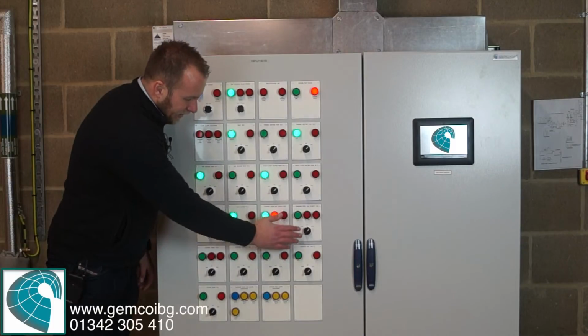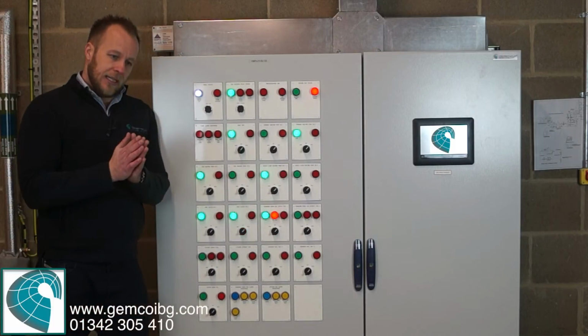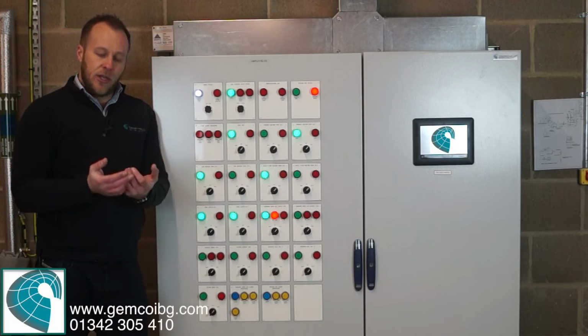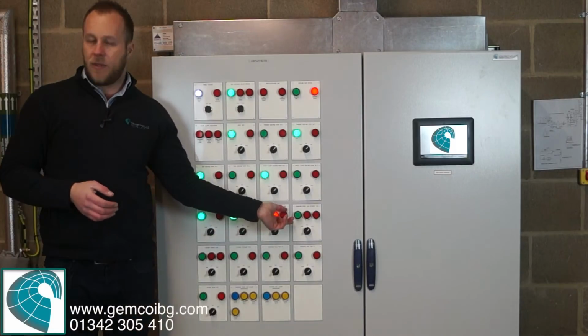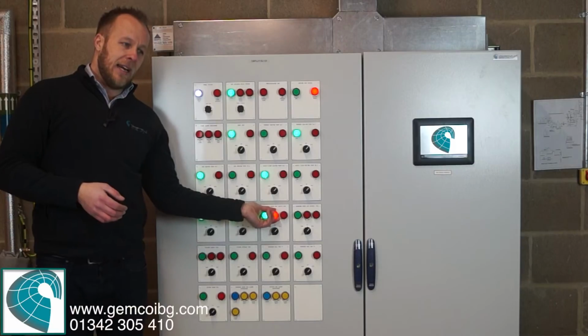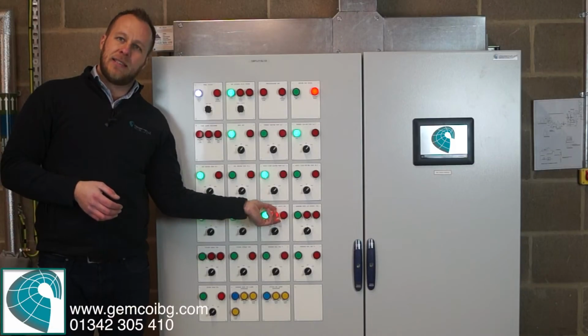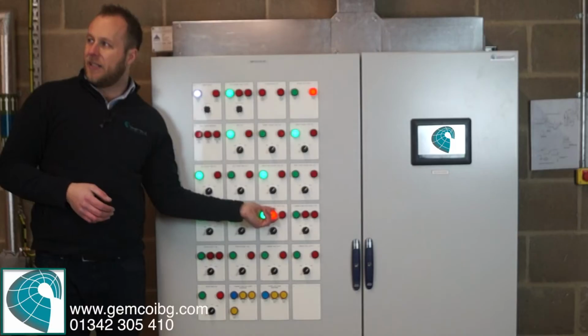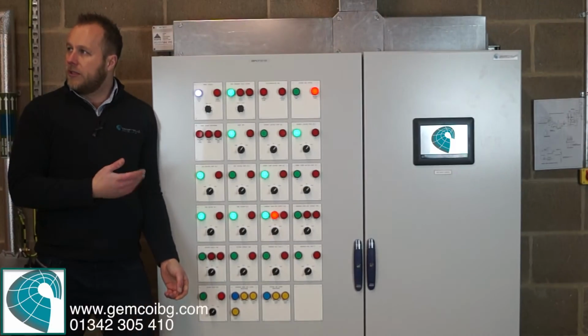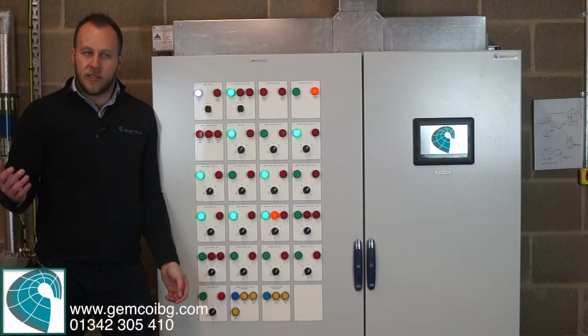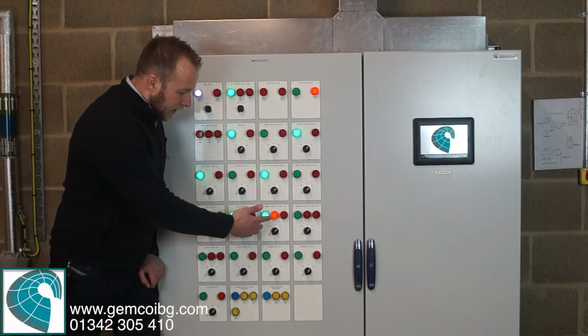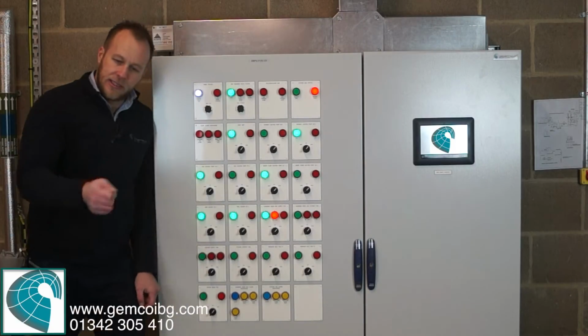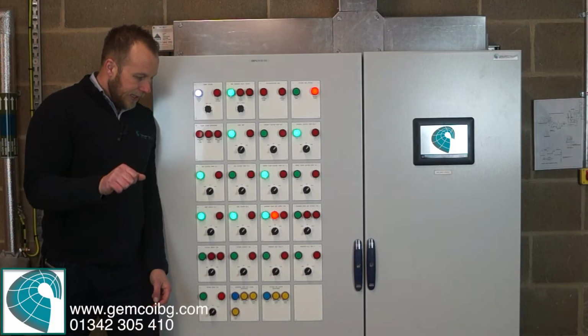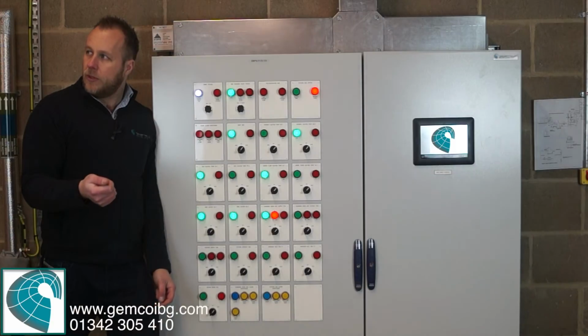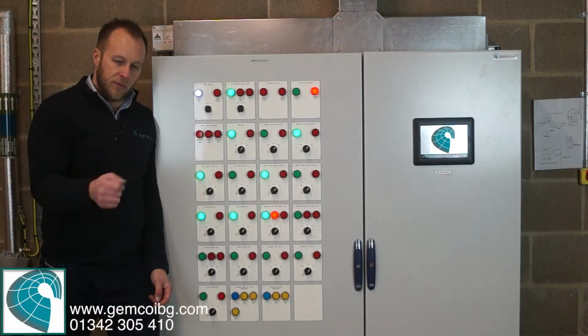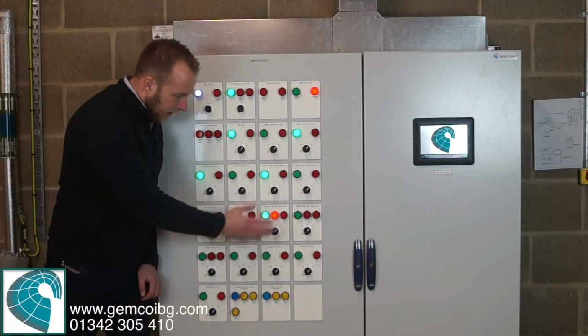With the ventilation, what you've got is CO2 air quality sensors in the changing room and in the drying room, and if the air quality is above a certain standard, it will bring the fan on to clear the air, to improve the air quality. Okay, now you can manually turn that fan on. There's key switches up there, and they will only run when you want to run them. So there's a key switch on the wall that says I want ventilation. You turn it on and it runs.